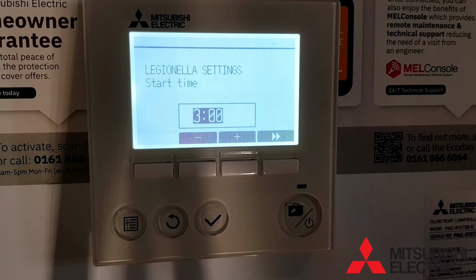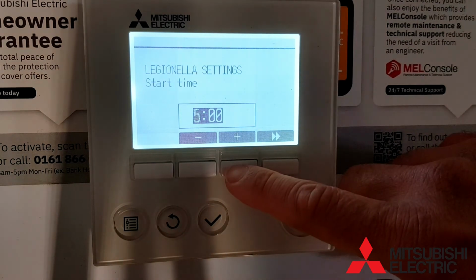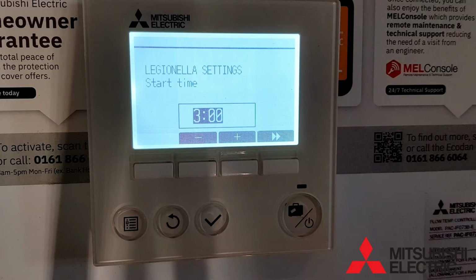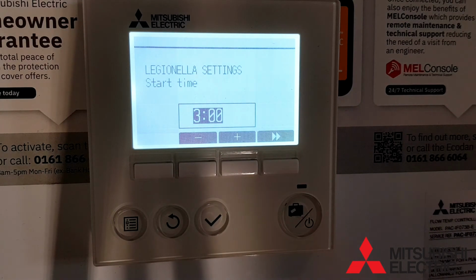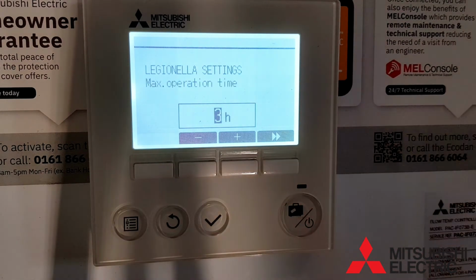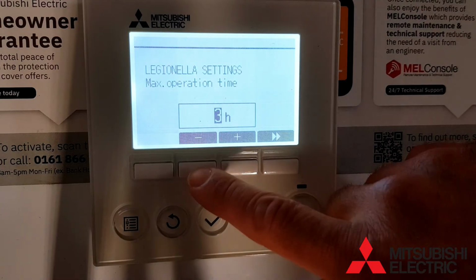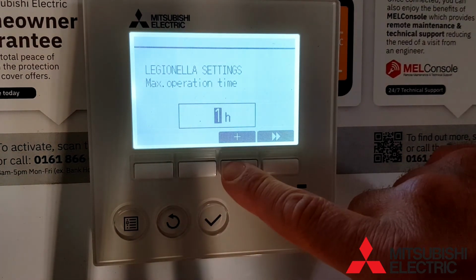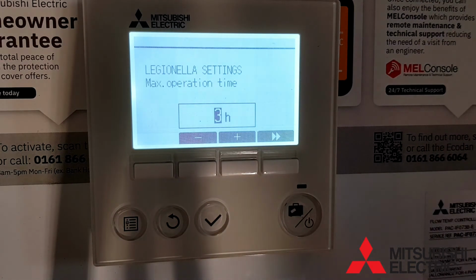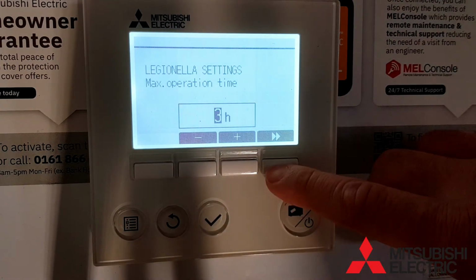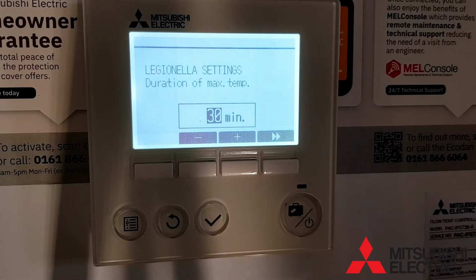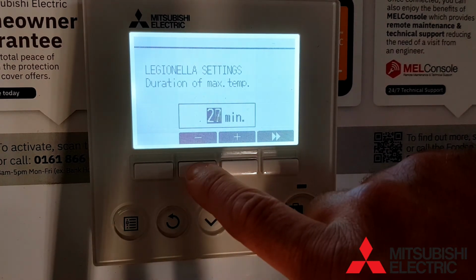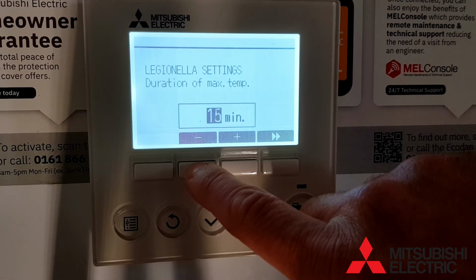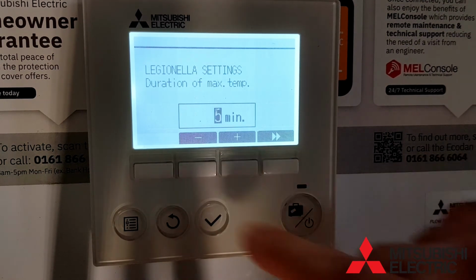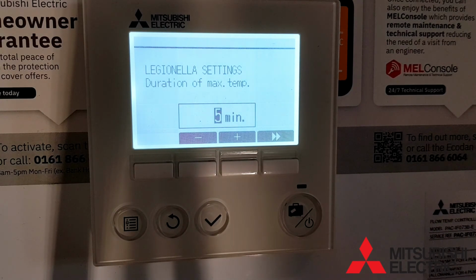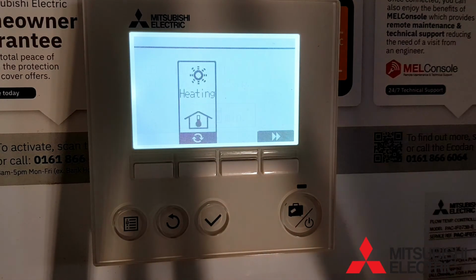Now we need to tell it what time to run the Legionella cycle. It is advisable to do this in the middle of the night when the electrical tariffs are the cheapest. So 3-4 o'clock in the morning would be ideal. Next is the duration of maximum temperature. It needs to hold the temperature above 60 degrees for at least 2 to 3 minutes to meet building regulations. As you can see, you can turn this up and down, but about 3 minutes is sufficient.